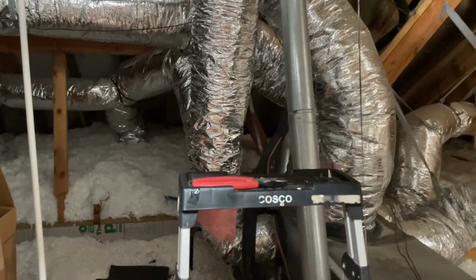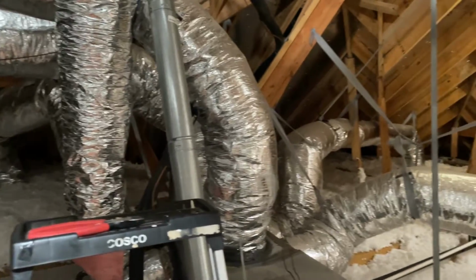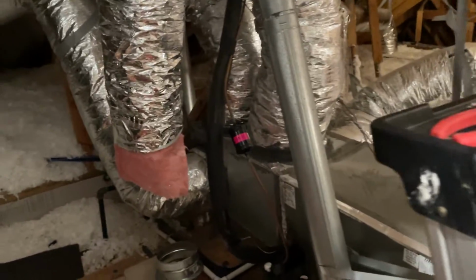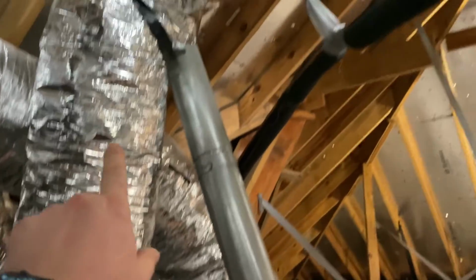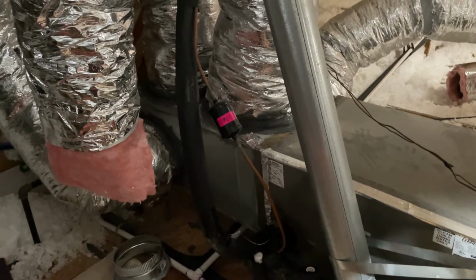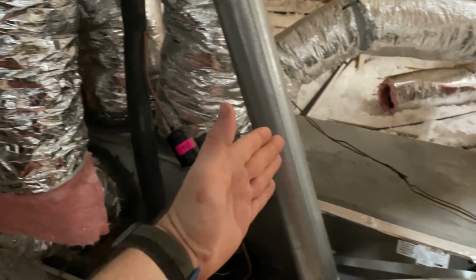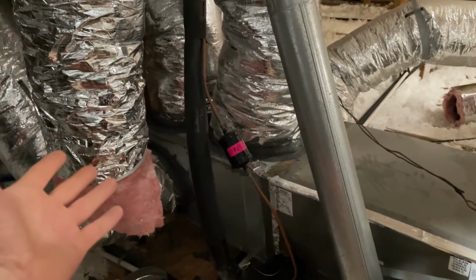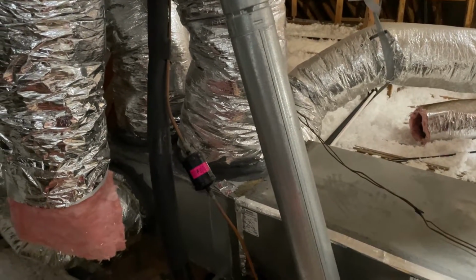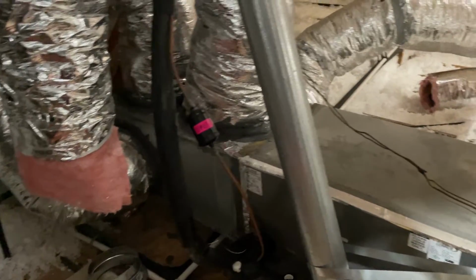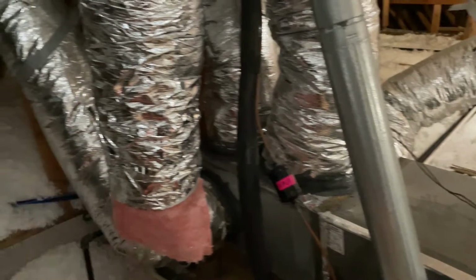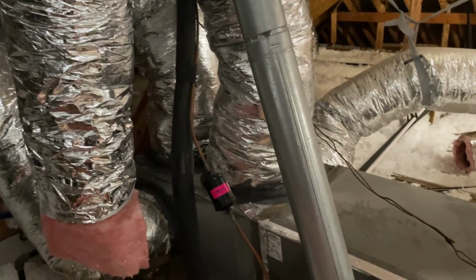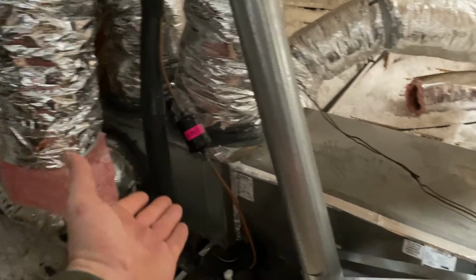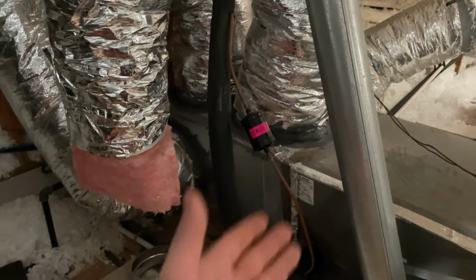That's if you're installing it into a central AC system, and there are some rules of thumb I'm going to violate just because I don't physically have the space here. This pipe right here, this duct coming up and over, is the duct feeding the supply of the main air conditioning unit. Ideally this would connect back about 2 feet so the dehumidifier air can mix with the rest of the air traveling through the system, giving it a chance to mix evenly among all the different ductwork exiting the supply. But I don't have the room — the coils are right there, the ductwork is right there, and there's a wall over there.